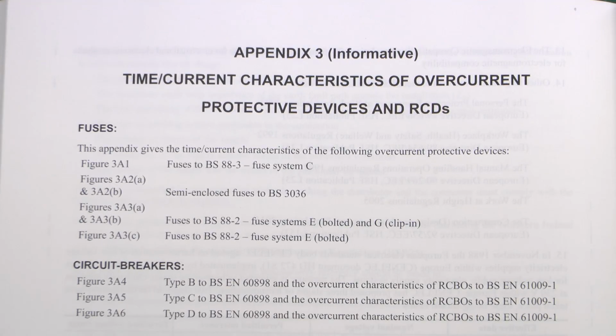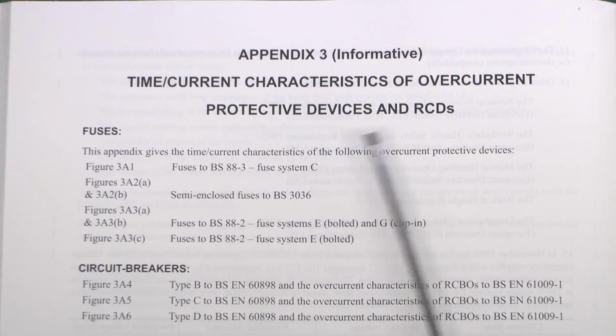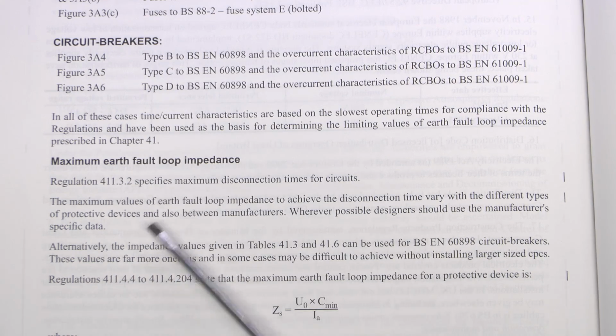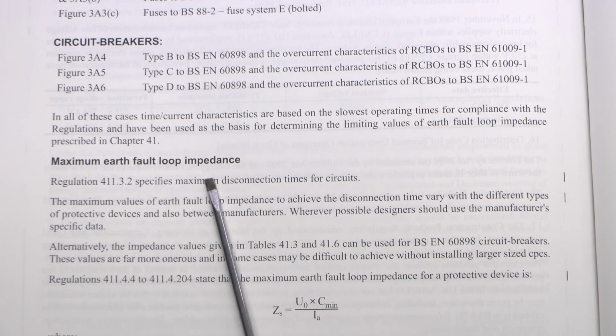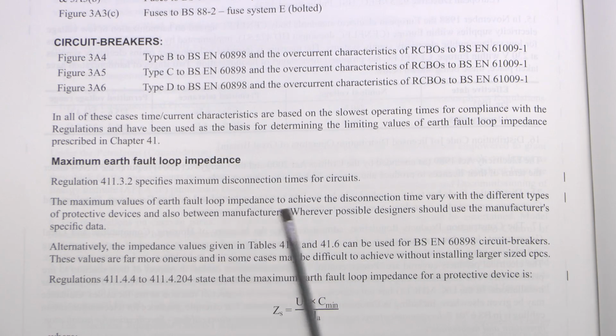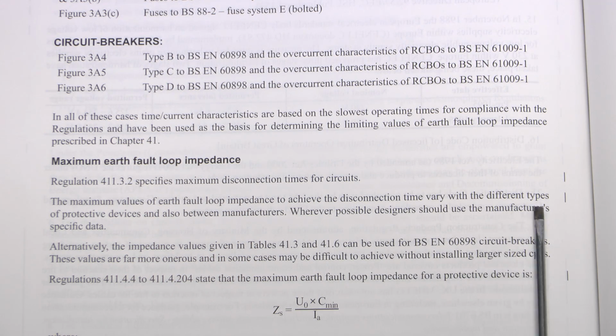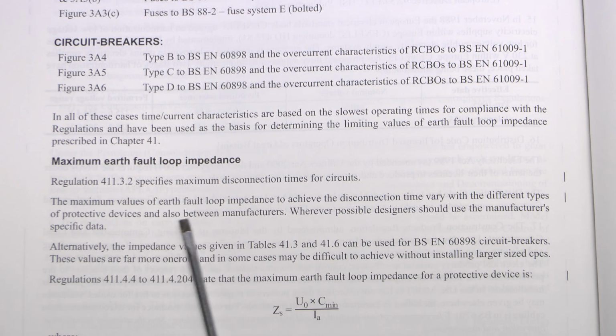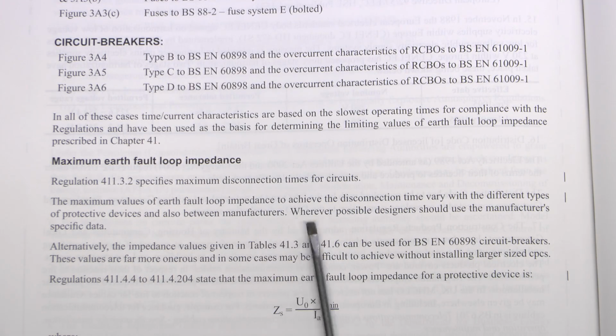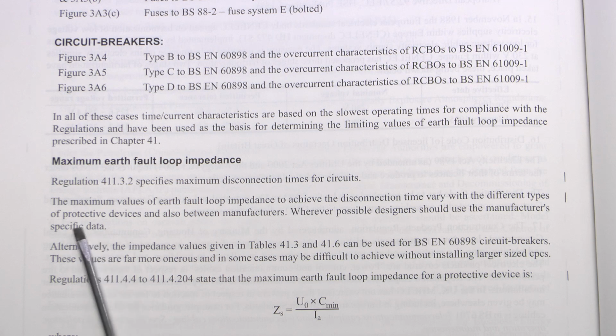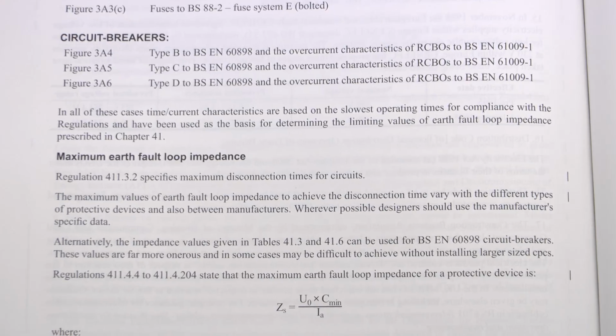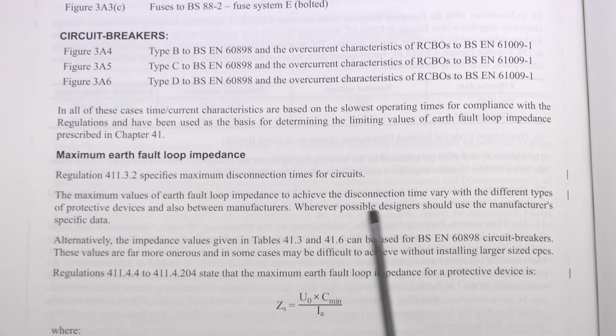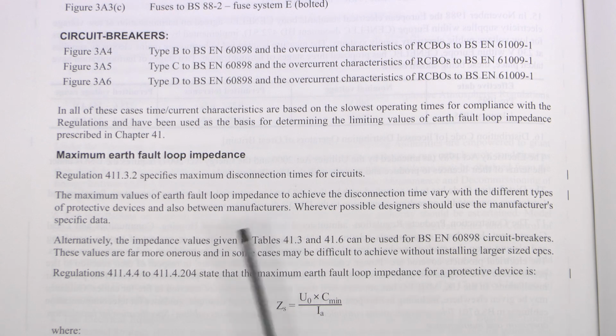Now Appendix 3, time current characteristics of overcurrent protective devices and RCDs. Something new here is under maximum earth fault loop impedance: the maximum values of earth fault loop impedance to achieve the disconnection time vary with different types of protective devices and also between manufacturers. This is an important bit - wherever possible, designers should use the manufacturer's specific data. Alternatively, you can still use the tables and calculations shown below. So you're supposed to use the manufacturer's data for a particular circuit breaker, fuse or whatever else, and in the absence of that, use the tables as previously.